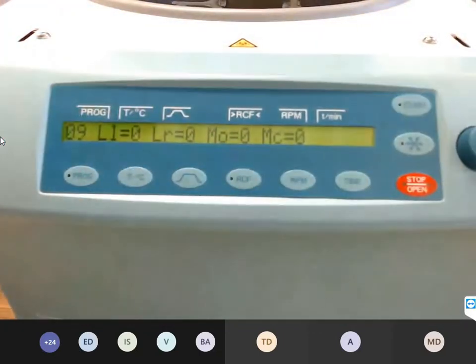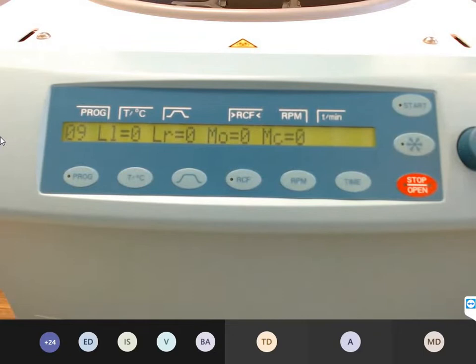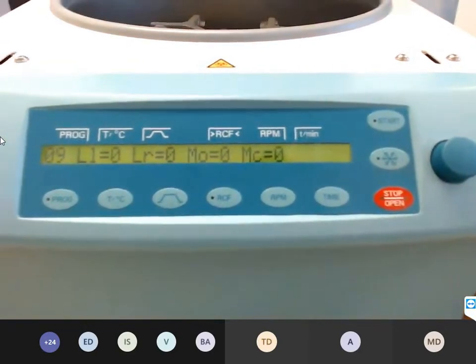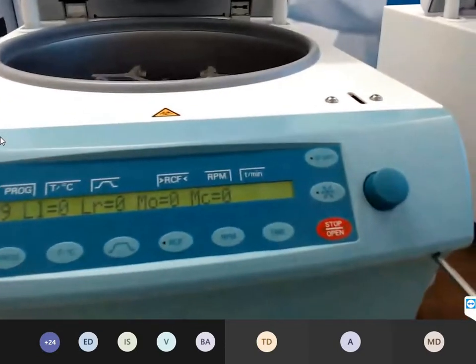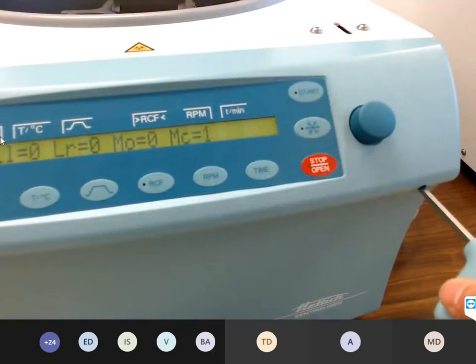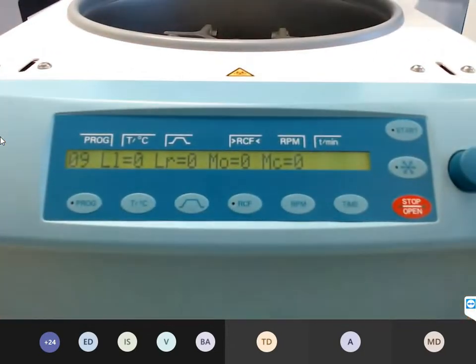We have a normally open and a normally closed. That's these two states. For this, you can use this Allen key. Go to the emergency hole and turn. Turn it. Now you can see the normally closed shows 1. It works. And the open one also works. Well, you can test it, for example, in case of error 6.